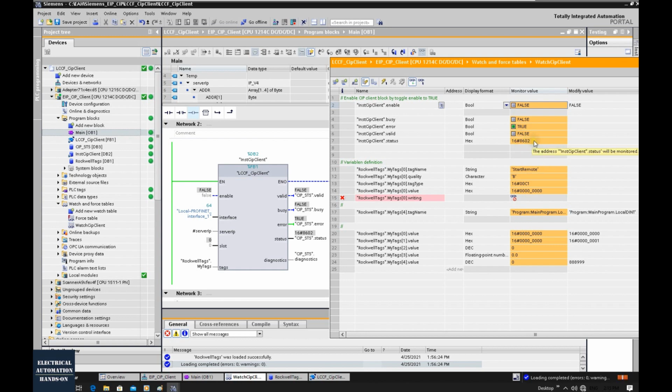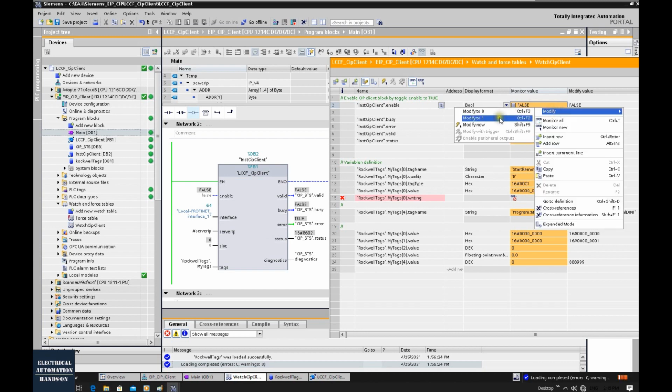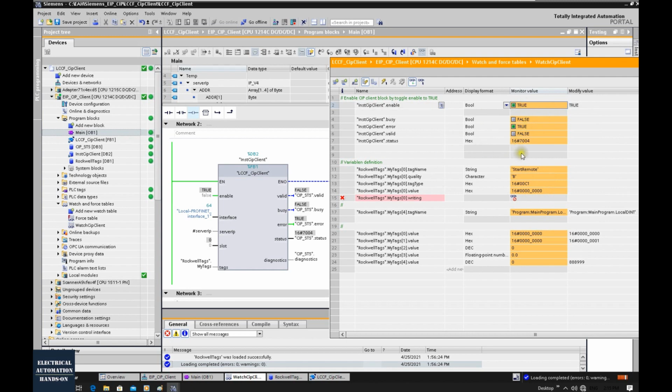Like in this case, if the communication cable disconnects, and after a couple seconds, the controller recovers the connection, we can do the logic to re-enable this communication. However, the system cannot recover itself. And from this input here, likely there's no way to restart or reset some internal status here. Likely the status will be stuck here. The system cannot recover itself.